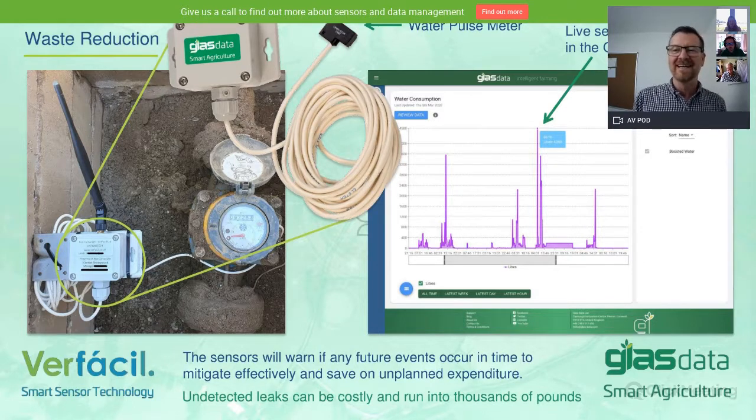Getting technical now, you'll want a technical answer: we take the LoRa radio device into the gateway, and we either push it to the cloud and convert it to MQTT, and then you can have an abstract MQTT driver in something like a Tridium JACE device, and we subscribe to an MQTT topic in your building controllers, and from there you can convert it to what you want: BACnet, Modbus, KNX. Or what we do is on the gateway hardware itself, we LoRa into the gateway, convert it to MQTT there, publish that MQTT topic to a broker, and then you subscribe to the MQTT broker from your BMS device. So yes, it can be done. And I've got two examples of that, Andy, if you want to see it. Okay.